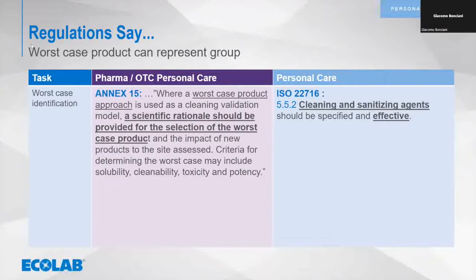If we talk about worst cases, because maybe you want to do a kind of grouping strategy - easy to clean, medium to clean, hard to clean - it's outlined even in the cosmetic GMP that cleaning and sanitization agents have to be specified and effective. So they should be effective for maybe your worst cases. This is why it can happen that you have another detergent for hard to clean products, or even an additive to a standard product, or maybe just a higher concentration of your standard product for these kinds of worst cases.